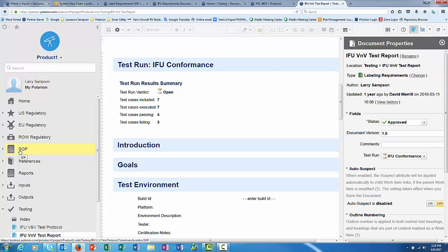So now it's not a question of recreation of all that. It's really a question of, is it still pertinent? So we would just walk through the design and say, has this requirement changed or not? And if the answer is no, then we not only have the sourcing relationships, but also the user needs, the design controls, the test cases, both verification and validation, and an initial understanding of what our performance was in the last product. So it's really powerful from the standpoint of the original creation of the file, but it's incredibly powerful from the standpoint of as we progress forward doing new designs and trying to categorize those designs as we go.